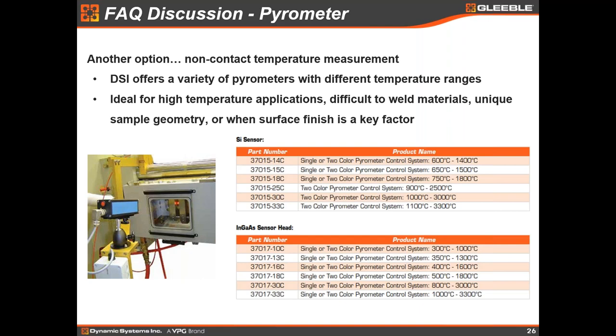Something we should also note is that we do have pyrometers for times when people can't use thermocouples. We've upgraded our pyrometers in the past five years, so if you used a pyrometer ten years ago with the Gleeble versus now, it's much easier. We typically use two-color pyrometers. We use them if you want non-contact measurement — going to very high temperatures, difficult-to-weld materials, unique sample geometry, or situations where surface finish is really important and you don't want that weld to interfere, say, with a wear test that might follow the Gleeble testing. Pyrometers are a very nice feature to use. If you have an older pyrometer, I'd reach out to Jake and his team, and they can find the right pyrometer for the temperature range that you're looking at.